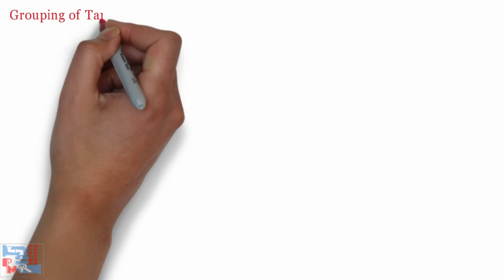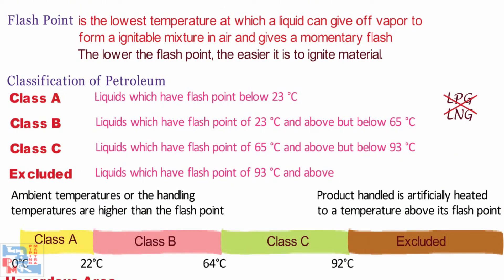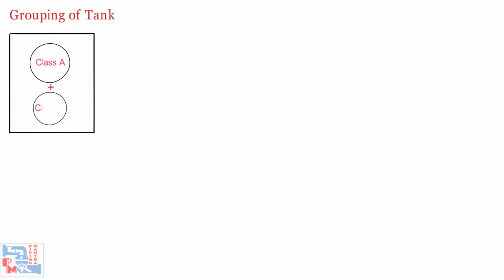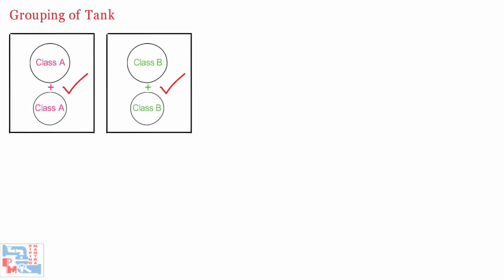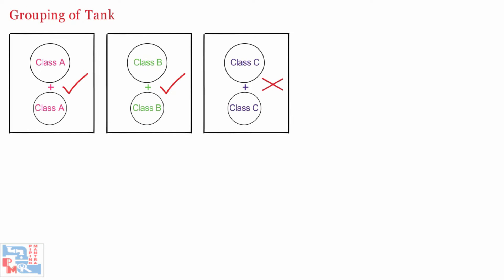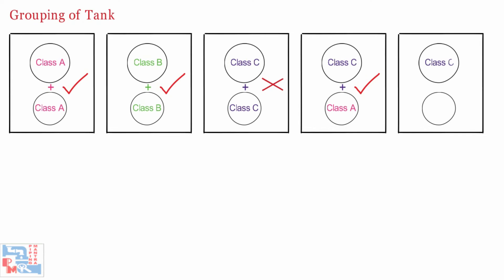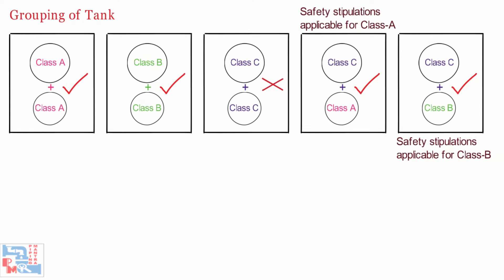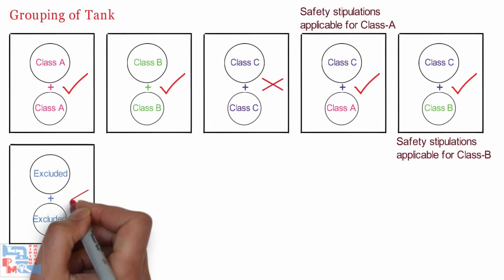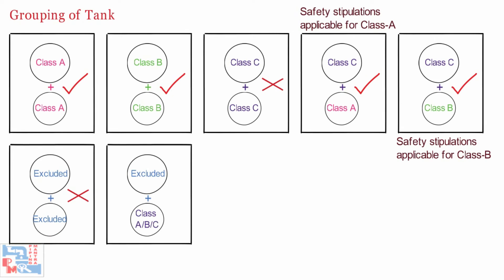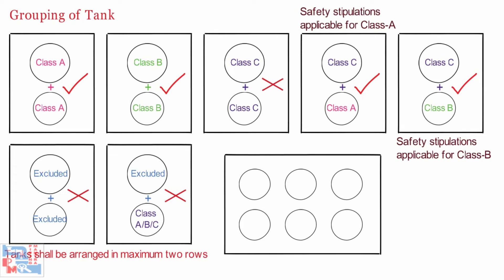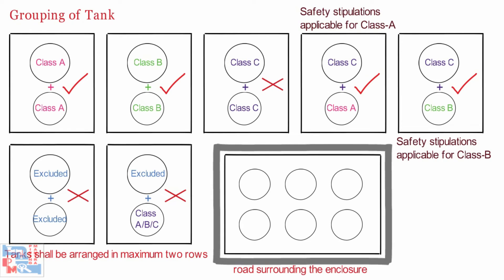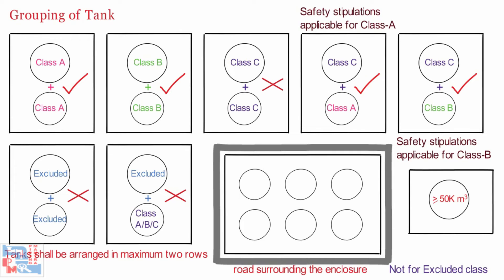Now let's talk about grouping. Grouping of petroleum products for storage shall be based on product classification. Class A and Class B petroleum may be stored in the same dike enclosure. Class C petroleum should preferably be stored in a separate enclosure; however, where it is stored in a common dike with Class A or B, all safety stipulations applicable for Class A or B respectively shall apply. Excluded petroleum shall be stored in a separate dike enclosure and shall not be stored with Class A, B, or C petroleum. In a dike, tanks shall be arranged in maximum two rows so that each tank is approachable from the surrounding road. Tanks having 50,000 cubic meter capacity and above shall be laid in a single row.